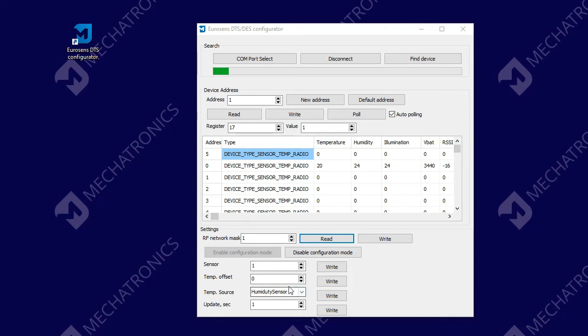The temp offset parameter is permanent temperature offset of the data and can be used for the calibration of the temperature sensor. We can change the source of temperature data by changing the temp source setting. It is possible to choose one of the 3 sources. Temperature sensors are built in the humidity sensor, radio link module, and central processor module. By default, humidity sensor is the main source of data. But some sensors don't have the humidity sensor option, therefore you can choose one of the remaining sources.